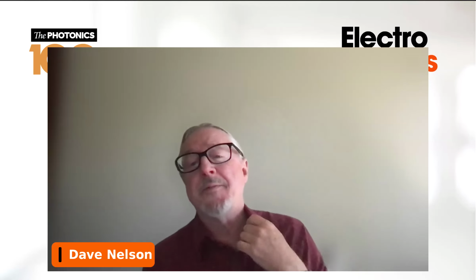Instrumental drift needs to be dealt with. And in general, optical methods are doing a complex spectral analysis to retrieve the isotopic composition. That's very different than mass spec, where they're just counting electrons. So that's an extra challenge. And the usual thing with many optical techniques, often you have a set of high reflectivity mirrors at the core of the instrument, and you need to keep them clean. That's also a little different than mass spec. But in summary, I think the opportunities are great for the places where optical methods can be applied.